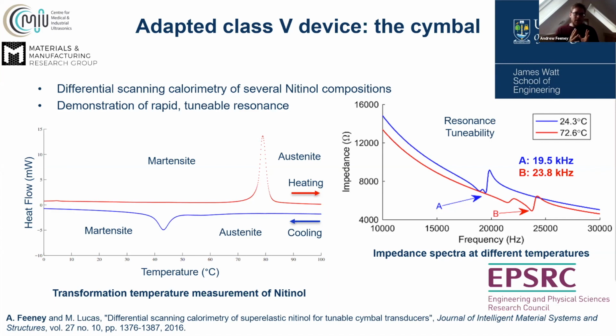I had identified issues with DSC. Residual stresses in the nitinol itself can cause accuracy problems for DSC, and this was particularly evident for superelastic nitinol. Superelastic nitinol is where the final transition to austenite is just above room temperature. In the context of this DSC plot, that would mean this spike between 70 and 90 would be shifted much lower, to around 20 to 30 degrees Celsius.